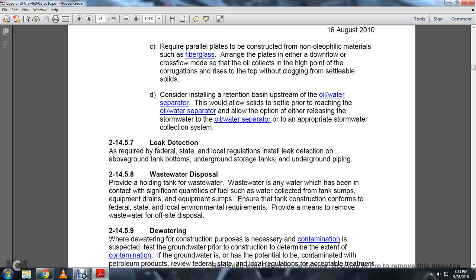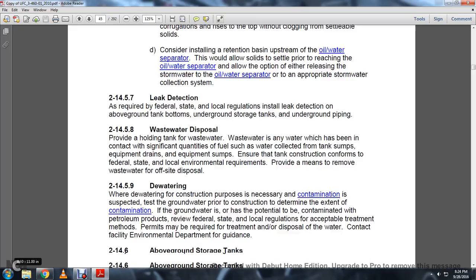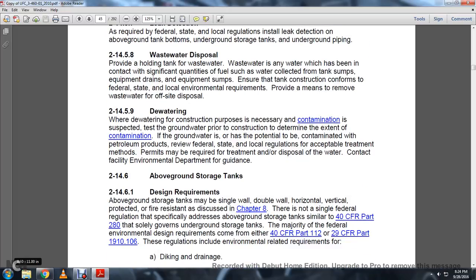Alright, 214.5.7 Leak detection as required by the federal, state, and local regulations. Install leak detection on aboveground tank bottoms and underground storage tanks and underground piping. 214.5.8 Wastewater disposal. Provide a holding tank for the wastewater, which is any water that has been in contact with significant quantities of the fuel, such as water collected from the tank sumps, equipment drains, and equipment sumps, ensuring the tank construction conforms to the federal, state, and local environmental requirements, and provide the means to remove the wastewater for off-site disposal.